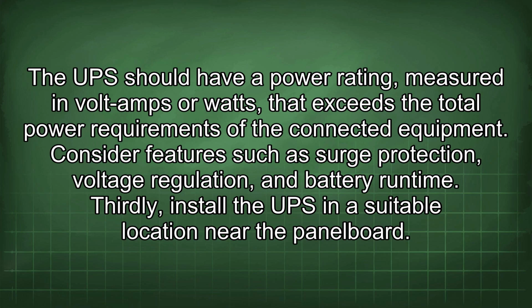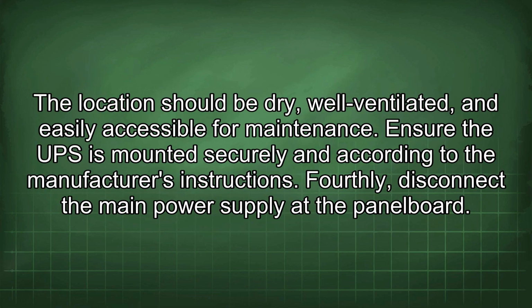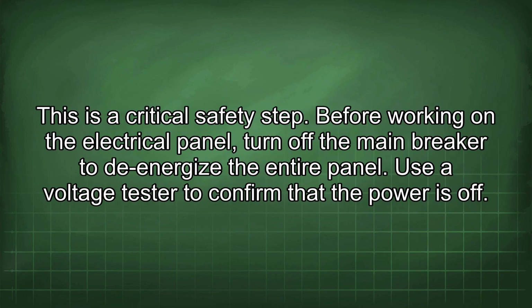Thirdly, install the UPS in a suitable location near the panel board. The location should be dry, well ventilated, and easily accessible for maintenance. Ensure the UPS is mounted securely and according to the manufacturer's instructions. Fourthly, disconnect the main power supply at the panel board. This is a critical safety step. Before working on the electrical panel, turn off the main breaker to de-energize the entire panel. Use a voltage tester to confirm that the power is off.